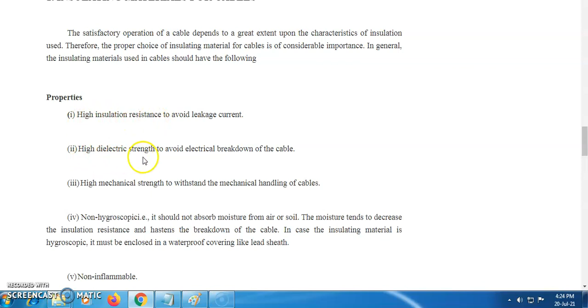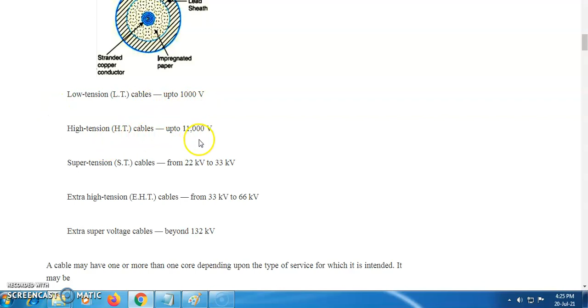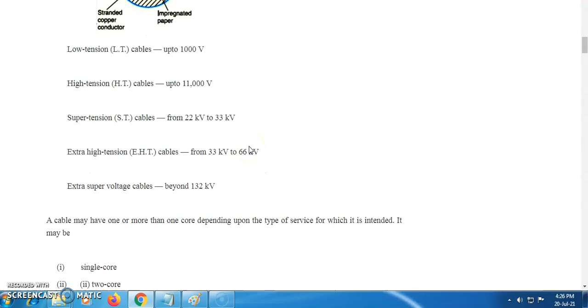Now we will discuss the classification of cables. The cables for underground service that we are discussing are classified by the type of insulating material used in manufacture and by the type of voltage. Here you will see low tension cables up to 1000 volts, high tension cables up to 11,000 volts or 11 kV, super tension cables up to 33 kV, extra high tension cables up to 66 kV, and extra super voltage cables beyond 132 kV. This is the classification of the cables based on voltage, right? And cables may be classified by the type of core: single core, 2 core, 3 core, 4 core type, right?